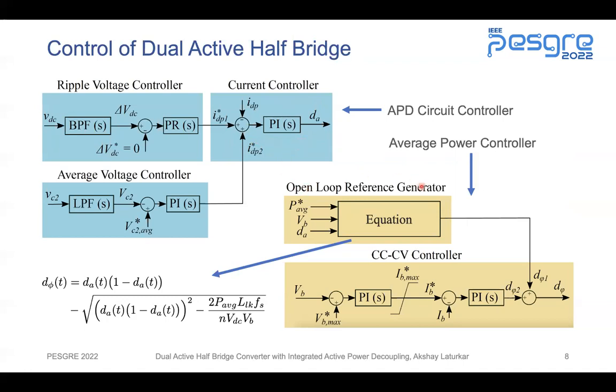For the average power controller, the phase shift is generated using an open loop reference generator. The phase shift required to transfer the average power is a function of the power to be transferred, the current battery voltage, and the duty cycle at which the APD circuit is operating. An expression is obtained for this, and the phase shift is generated using this idealistic equation. Any correction factor due to circuit non-idealities and parameter variations is generated using a traditional CCCV controller, and the respective phase shift is generated.